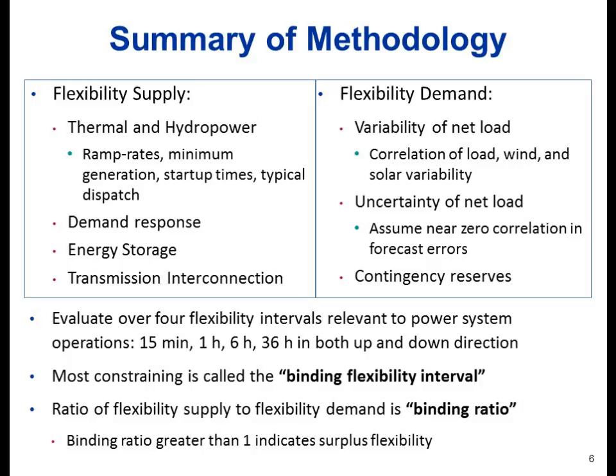Now, on the other hand, flexibility demand depends on the variability and uncertainty of the net demand. We characterize the variability of load, solar, and wind over these different time intervals, along with the correlation between the different sources. And we did this based on 4 different data sets from regions in the West. We then calculate the net demand variability for a portfolio based on its peak load, its solar capacity, and its wind capacity in the portfolio.